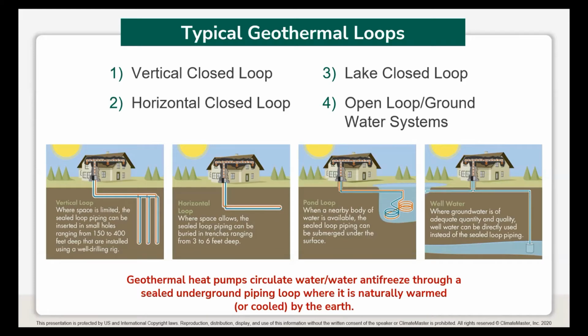Another loop is a horizontal one. We need a little bit more real estate to dig down 5 feet into the ground, where we can bury a series of ground loops functioning identically to the vertical bores when designed correctly. Probably the least expensive ground loop would be one that we would sink into a pond or hang underneath a dock in deep water. A very efficient and relatively inexpensive ground loop.